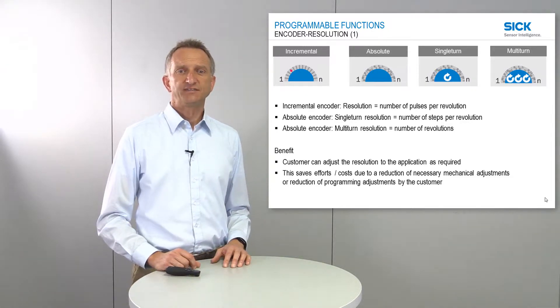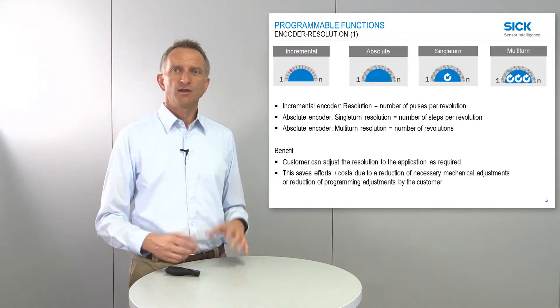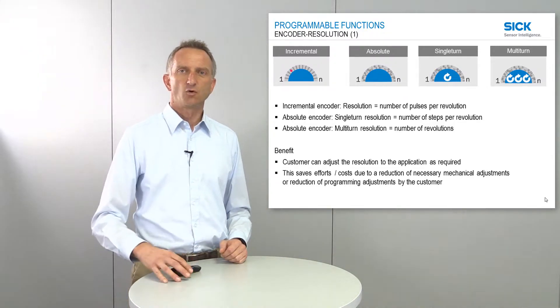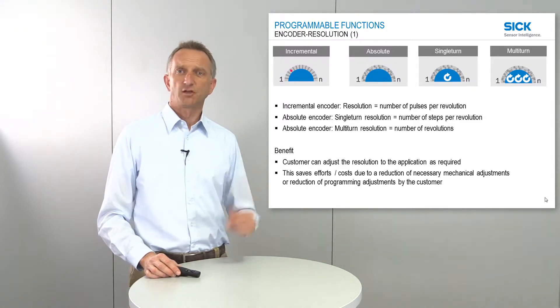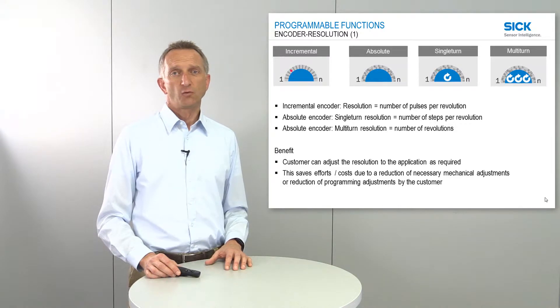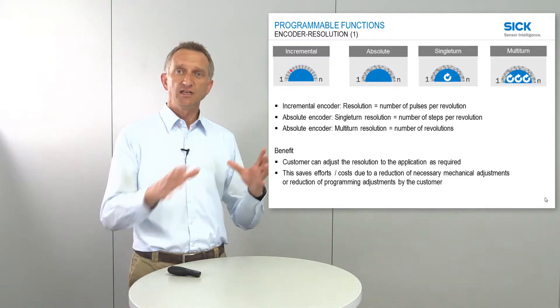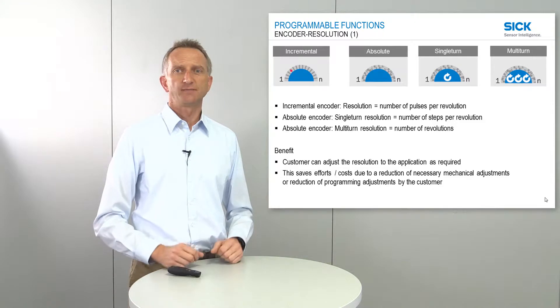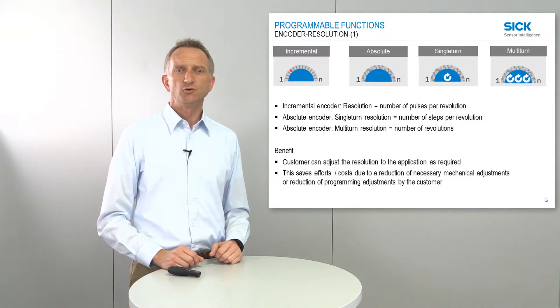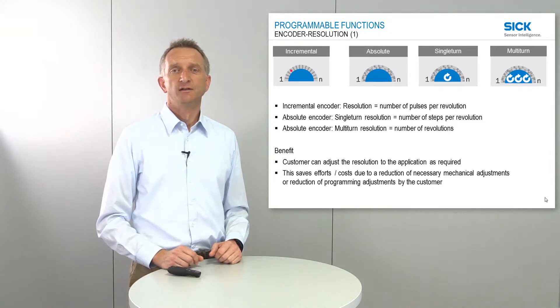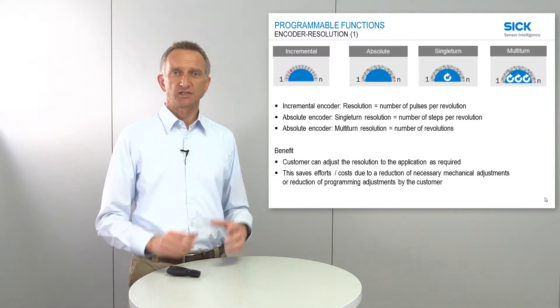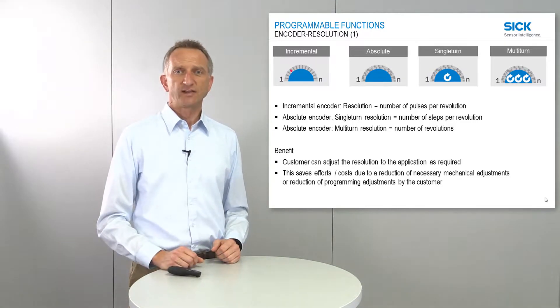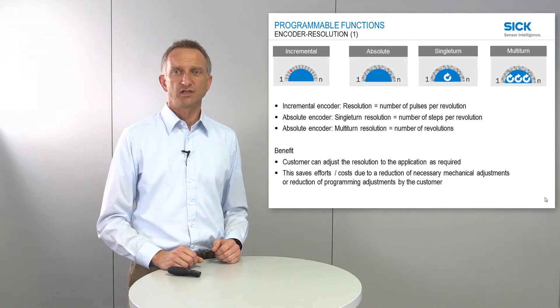The benefit of this is very clearly that the customer can directly and easily adapt the encoder and encoder resolution to his application, and this saves a lot of effort. For one thing, on the mechanical side, there is no need for mechanical adaption on the application. But it also notably reduces programming efforts on the PLC side, because this adaption of encoder resolution can easily be done directly on the encoder and does not need to be programmed on the PLC engineering tool side.